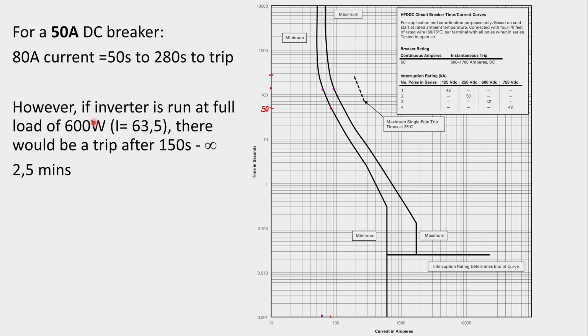And I'm also aware that if I run the inverter at full load, 600 watts, maybe I run it for half an hour, it might trip after 2.5 minutes, but judging from these tripping curves, it might not at all. So it's a little bit of a gray area here. Maybe I could have gone to a 55 amp circuit breaker and then it would never trip on full load. But I'm fine with the 50 amp circuit breaker because I have that in stock. And with protection, we tend to always go a little bit lower than higher.